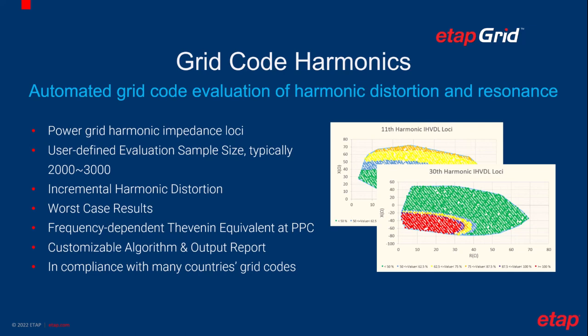It considers various power grid harmonic impedance conditions with the typical grid code requirements of 2,000 to 3,000 sample size. It takes double the number of calculations in the background, which means 4,000 to 6,000 harmonic load flow and frequency scan calculations. As a result, it provides incremental harmonic distortions, the worst case conditions, at the point of common coupling. Due to different interpretations and requirements from different power grids, the algorithms and output reports are customizable.